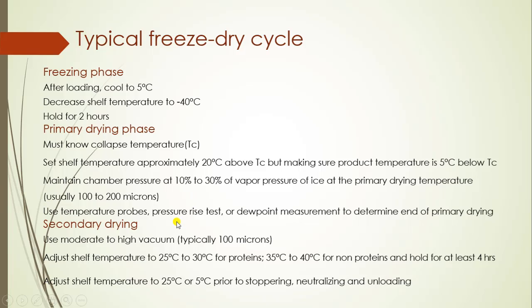Use temperature probes, pressure rise tests, and dew point measurements to determine the end of primary drying. For secondary drying, use moderate to high vacuum. Adjust the shelf temperature to 25 to 30 degrees Celsius for proteins and 35 to 40 degrees Celsius for non-proteins, and hold it for at least 4 hours. Then adjust the shelf temperature to 25 degrees Celsius or 5 degrees Celsius prior to stoppering, venting, and unloading.